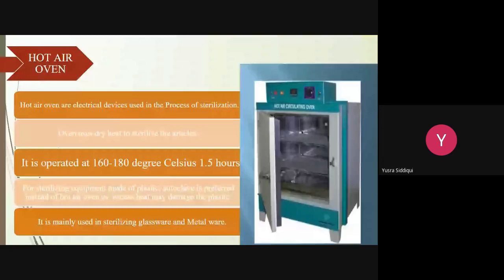Dry heat destroys bacteria and endotoxins which are difficult to eliminate by other means, and this property makes it applicable for sterilizing. Dry heat kills by oxidation, protein denaturation, and toxic effects of elevated levels of electrolytes. How can we use the hot air oven? Articles to be sterilized are first wrapped or enclosed in containers of cardboard, paper, etc. Then the materials are arranged to ensure uninterrupted airflow. The oven may be preheated for materials with poor heat conductivity. The temperature is allowed to fall to 40 degrees centigrade to remove all the sterilized materials.